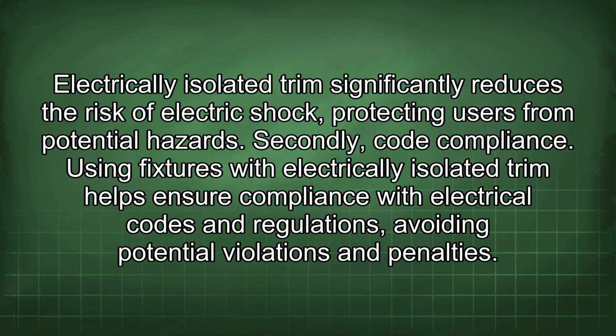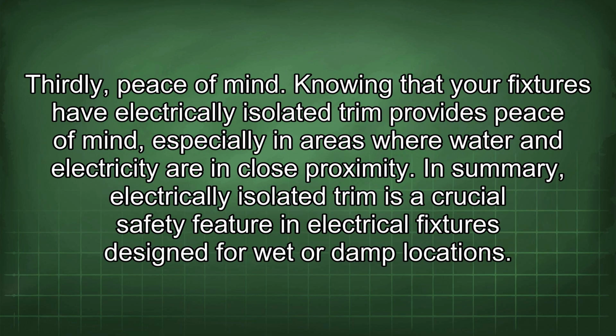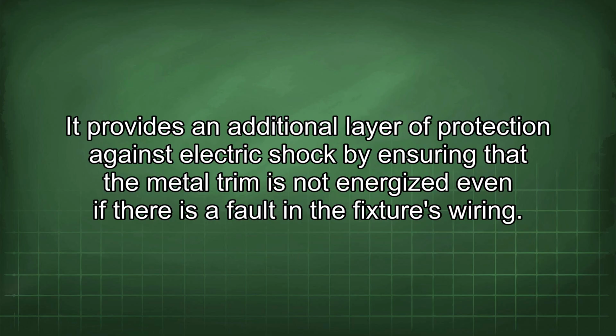Secondly, code compliance. Using fixtures with electrically isolated trim helps ensure compliance with electrical codes and regulations, avoiding potential violations and penalties. Thirdly, peace of mind. Knowing that your fixtures have electrically isolated trim provides peace of mind, especially in areas where water and electricity are in close proximity. In summary, electrically isolated trim is a crucial safety feature in electrical fixtures designed for wet or damp locations. It provides an additional layer of protection against electric shock by ensuring that the metal trim is not energized even if there is a fault in the fixture's wiring.